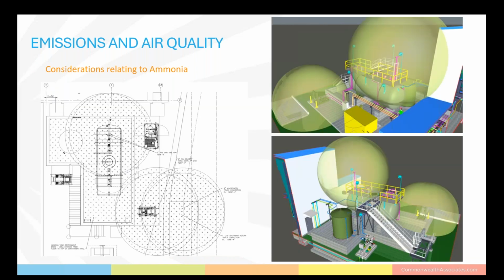We talked a little bit about hazardous area classification in the fuel gas section. NFPA 70 and NFPA 497 defines vapor from aqueous ammonia to be considered a Class 1 Group D hazard. Because of that designation, hazardous areas need to be identified using the same ammonia storage as before. The plan view on the left shows those hazardous areas, and the two model shots show them in 3D space. Similar to the gas yard, these spaces are part of the model and layout and need to be considered for electrical equipment and life safety egress considerations in this area.